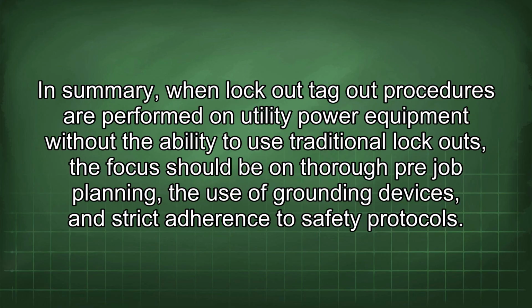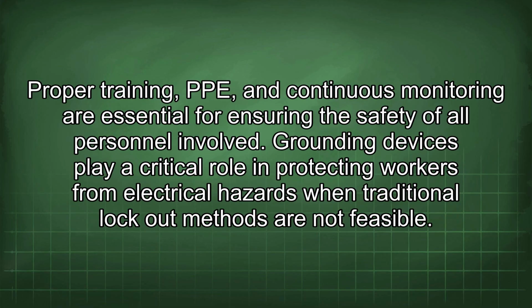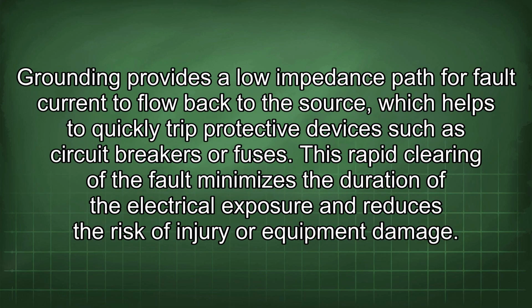In summary, when lockout tagout procedures are performed on utility power equipment without the ability to use traditional lockouts, the focus should be on thorough pre-job planning, the use of grounding devices, and strict adherence to safety protocols. Proper training, PPE, and continuous monitoring are essential for ensuring the safety of all personnel involved. Grounding devices play a critical role in protecting workers from electrical hazards when traditional lockout methods are not feasible. Grounding provides a low impedance path for fault current to flow back to the source, which helps to quickly trip protective devices such as circuit breakers or fuses.